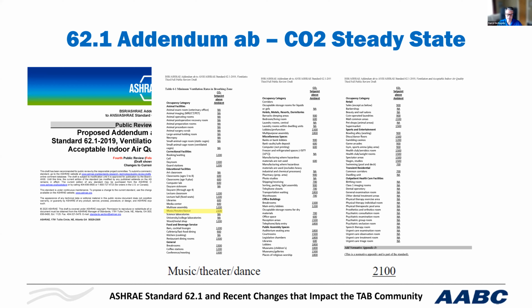Let's take an example of that, a movie theater, where you have a set number of seats and you have a set number of tickets. They know what time the movie starts. They know how many tickets they sold for the movie. So they can count the number of tickets sold, multiply by the ventilation rate that's required for that space, and modulate the damper to that number. Very quick and easy, instead of waiting 1 hour for the space to become steady state.